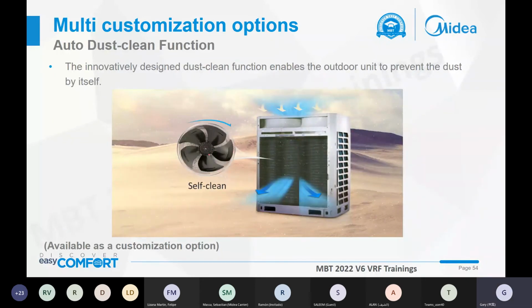And another customization option is the auto dust cleaning function. I think deserts are not very common in Latin America, so this function may not be used very often. This function is called self-clean. Normally the unit runs in one direction, and the dust will be on the opposite side in the coil. If the fans run in the reverse direction, this dust will be blown out. So this is the dust cleaning function principle.